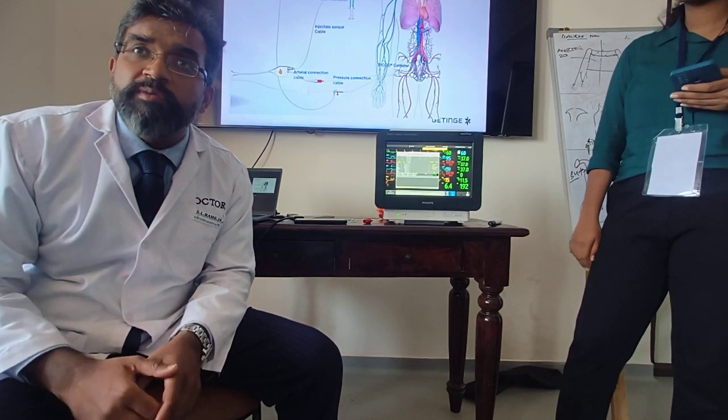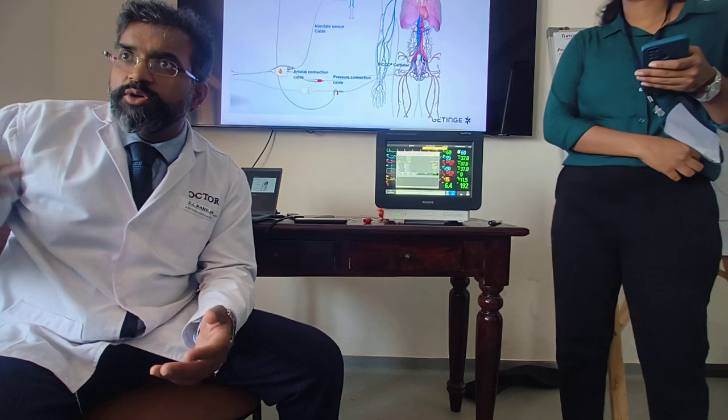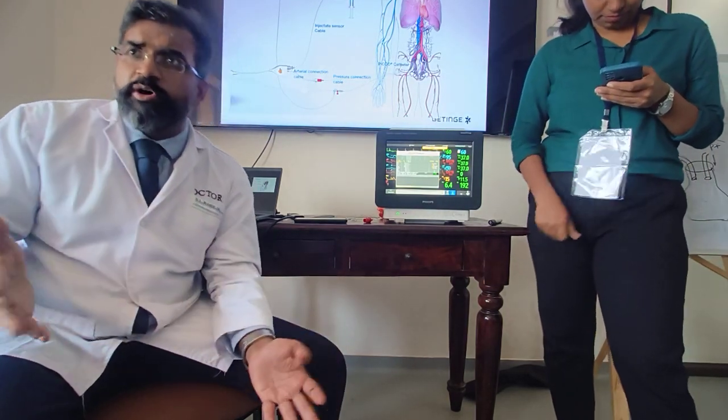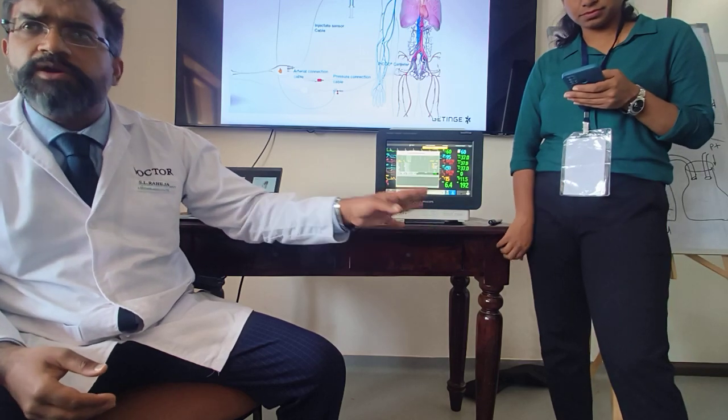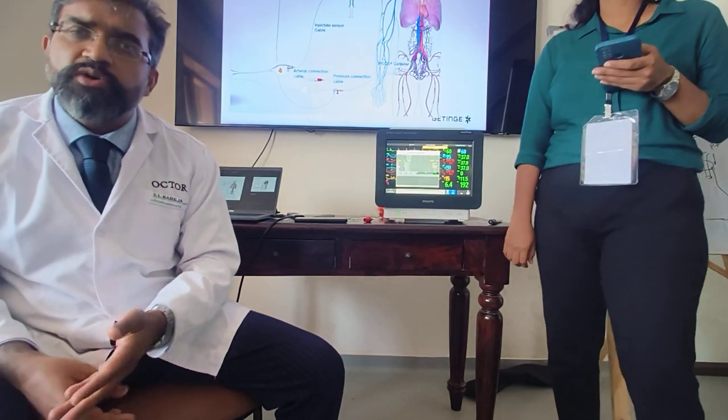What happens to your IBP pulse waveform? It completely changes, no? It becomes different. So if your waveform becomes different, will it be able to identify your continuous cardiac output? No, because it looks at waveform characteristics to monitor your cardiac output. So it cannot work with IBP.